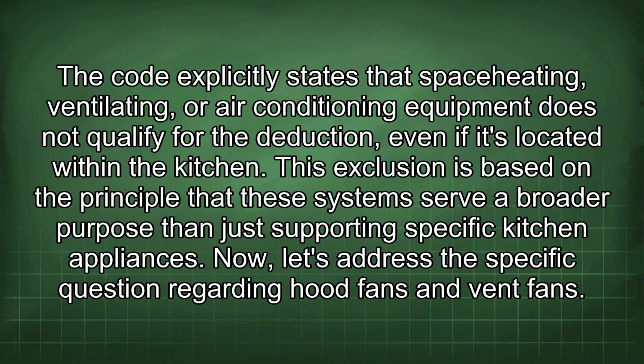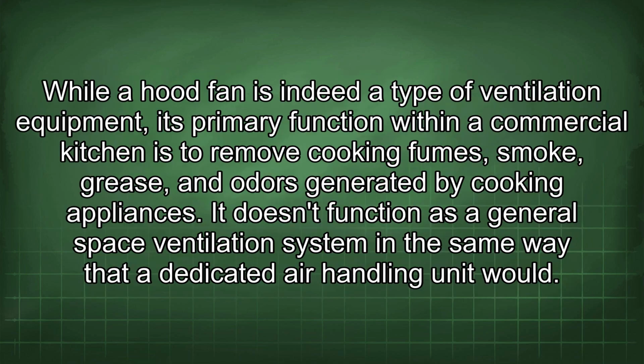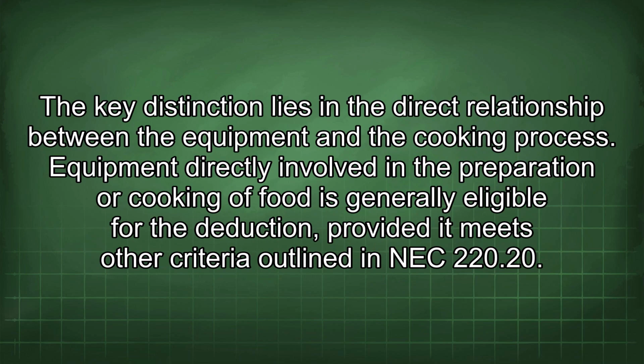Now, let's address the specific question regarding hood fans and vent fans. While a hood fan is indeed a type of ventilation equipment, its primary function within a commercial kitchen is to remove cooking fumes, smoke, grease, and odors generated by cooking appliances. It doesn't function as a general space ventilation system in the same way that a dedicated air handling unit would. The key distinction lies in the direct relationship between the equipment and the cooking process.